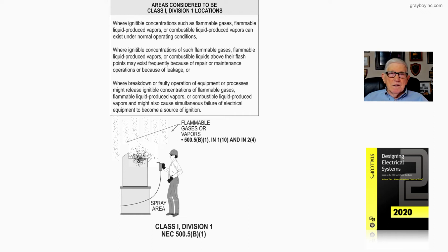And then, of course, we'll get into this as we get on into the presentation, but you select your equipment in 500.7 based upon the equipment being explosion-proof, purged and pressurized, or intrinsically safe. 500.7 lists this equipment along with Article 504 for intrinsically safe. And then, of course, you'd go to 501.10, excuse me, and select your wiring method in A.